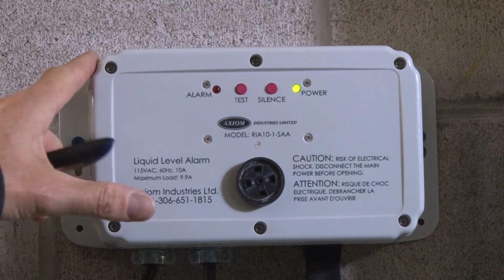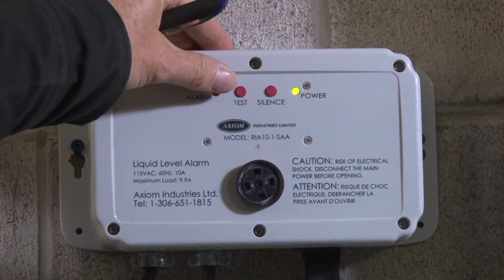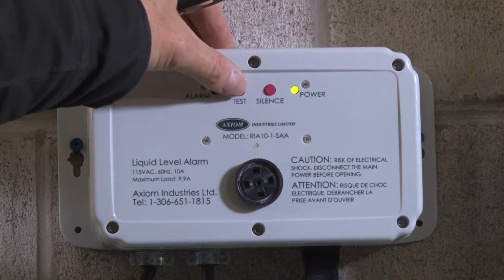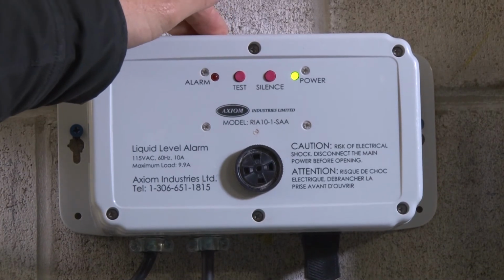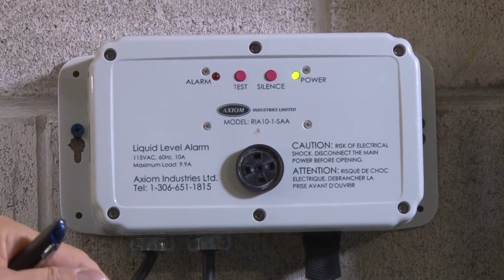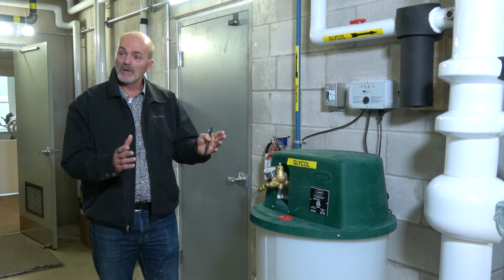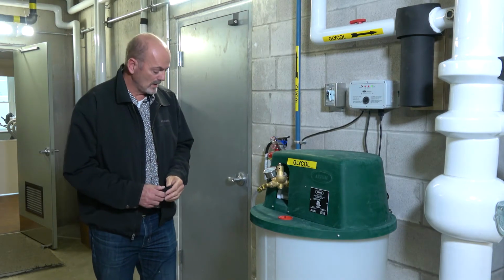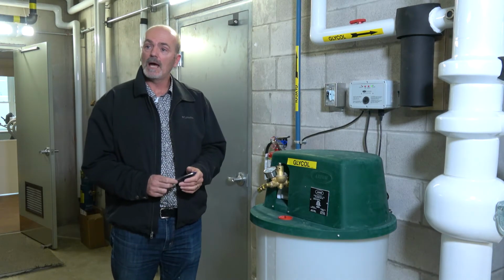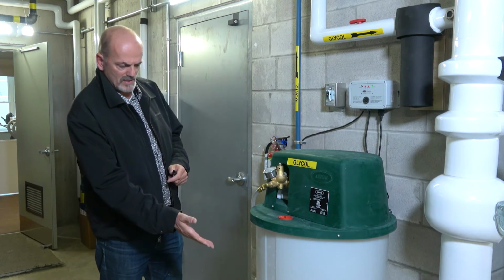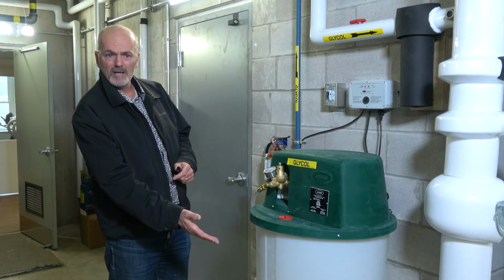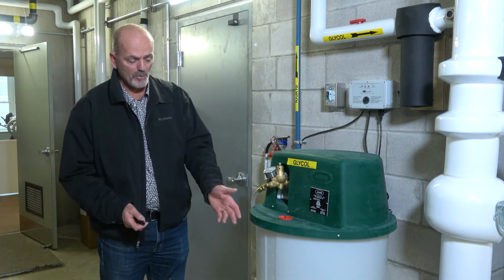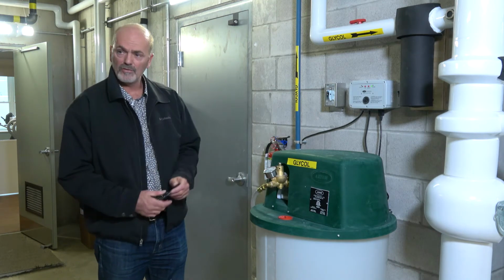So I think we can mimic this here just strictly by hitting the test button. Is that correct? Okay, there's your alarm. And that will indicate it's time to come down and check things out. I'm not sure if you're going to be adding pre-mixed glycol. I see a glycol pail there. Is that glycol? Okay, so that pre-mixed glycol can get added into the system.